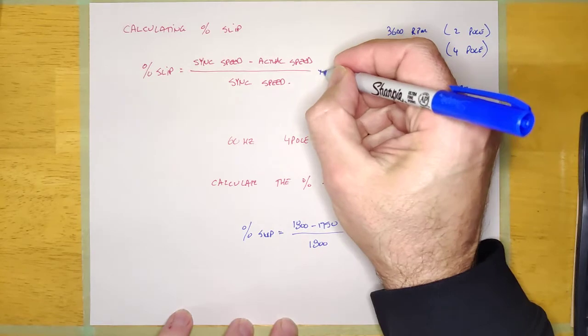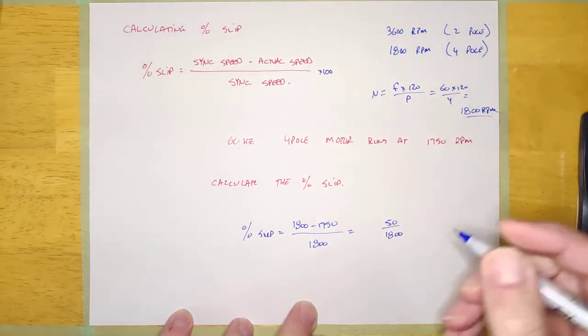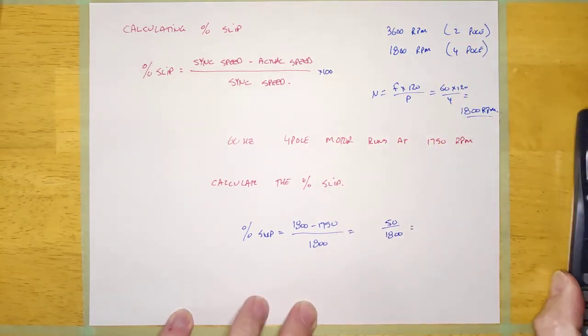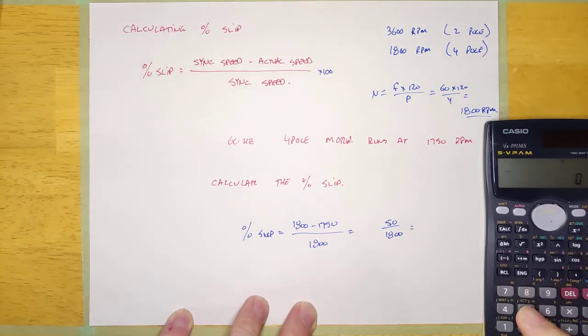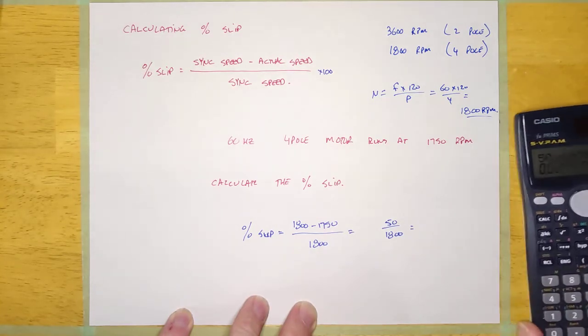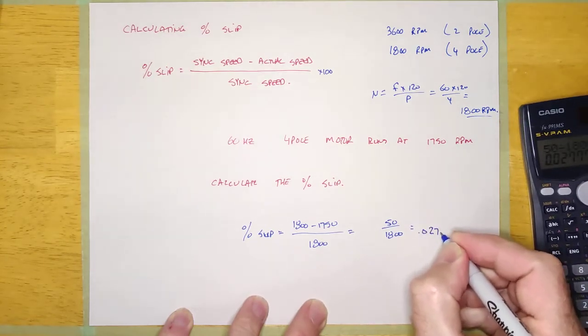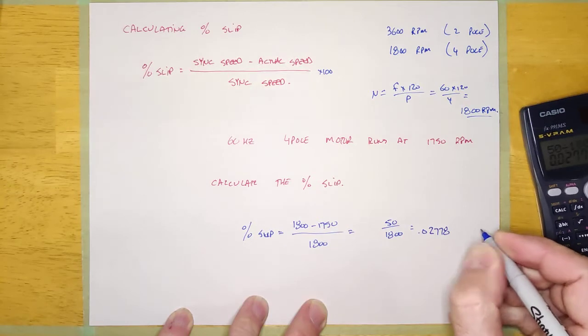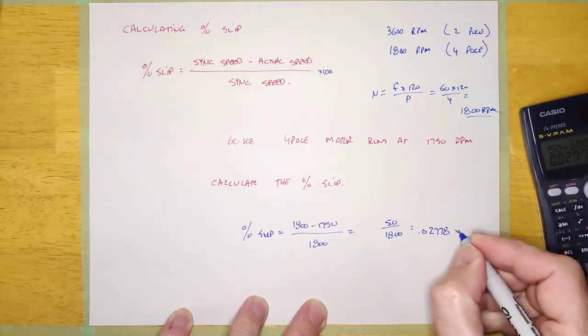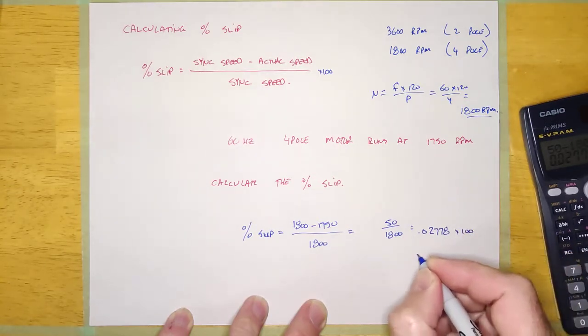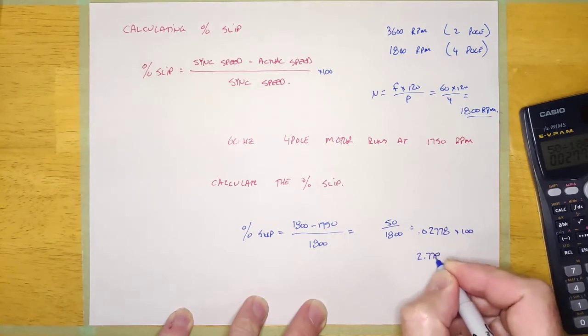And that's going to give you the percent it's slipping of the sync speed. And you have to actually multiply this by 100, or else it's going to be in a decimal. So if I go 50 over 1,800, it comes to 0.02778. And if I multiply that by 100 to get that into the percentage, it's going to be 2.778%.